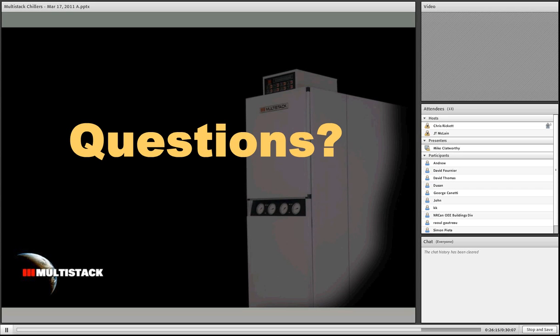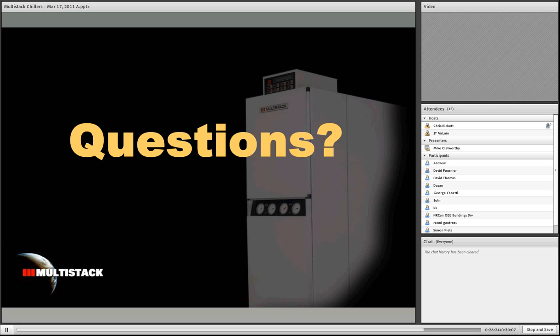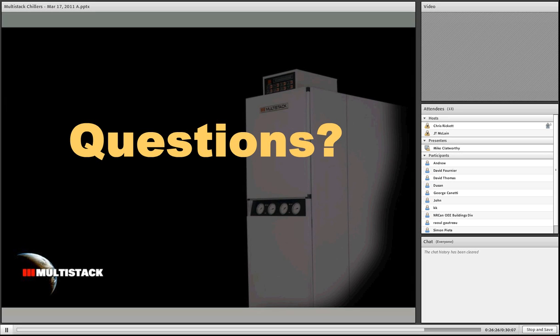Most of the time when we think about heat recovery chillers of conventional design, if you were thinking Trane, Carrier, York, McQuay, a conventional type machine, they would probably want to limit you to about 130, 135 degrees. We actually have 3 different tiers of temperature available, up to 140, up to 160 F or 180 F. So we can make hot water efficiently up to 180 degrees Fahrenheit.